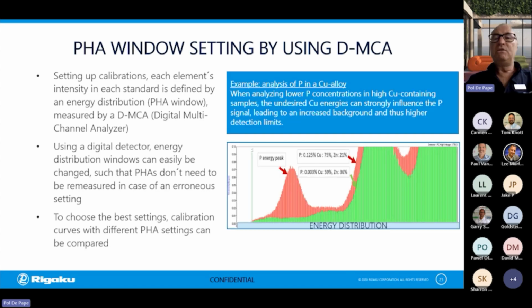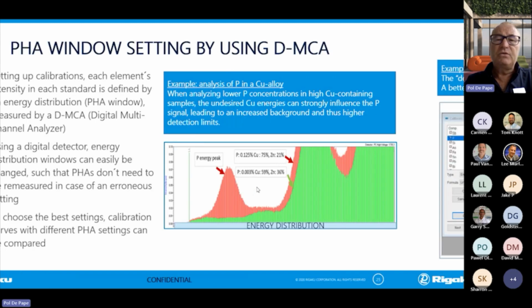So what does this mean? By means of an example, phosphor in a copper alloy. Phosphor has a changing concentration as well as copper. If we now look in the PHA window down here, we can see huge copper peaks at the right, and those copper peaks may disturb the analysis of phosphorus, especially when the concentration of phosphorus is low. Depending on the window that we set, we can see here at the left the LL, which is the lower limit. The upper limit isn't visible here. But anyway, we can change those levels.